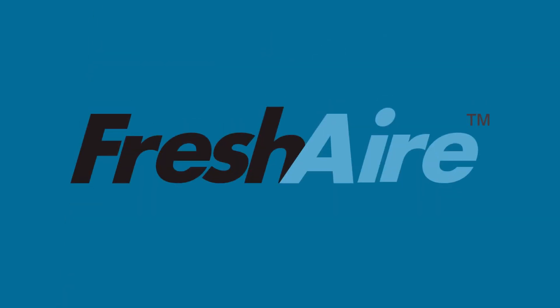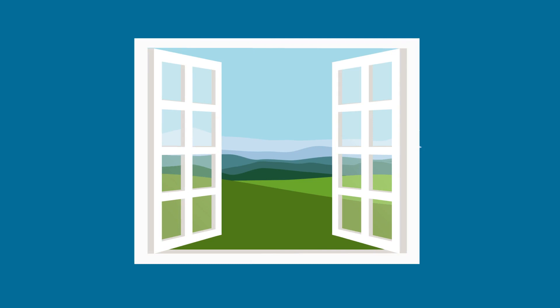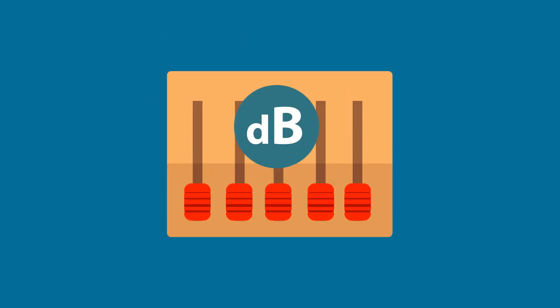The award-winning FreshAire system is also unique to Friedrich, with several patents pending. Instead of using an energy-robbing secondary preconditioning coil and compressor, the Friedrich FreshAire PTAC brings in the outside air through a specially designed manifold, passes the raw air through a MERV8 filter, and introduces the air directly into the primary evaporator coil along with the room return air. This is a much more elegant and efficient method for conditioning the outside air, with improved sound quality and higher unit efficiencies.